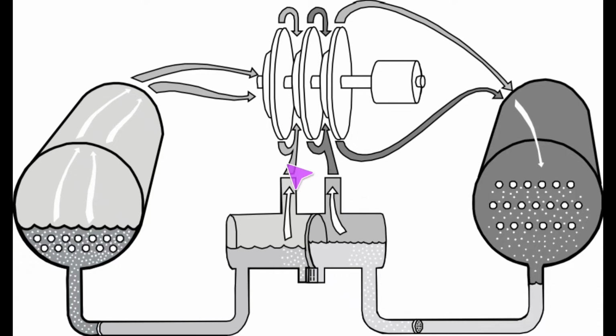This is another way to identify, am I looking at a CVHE or a CVHF? A CVHE is going to have a 2-pipe economizer coming off the top for the vapor gas. So diving into that a little bit deeper, we're coming from the condenser into the first stage flash. That flashes off. It's the same exact scenario as the CVHF. So we're dealing with an 80-20% ratio, right?